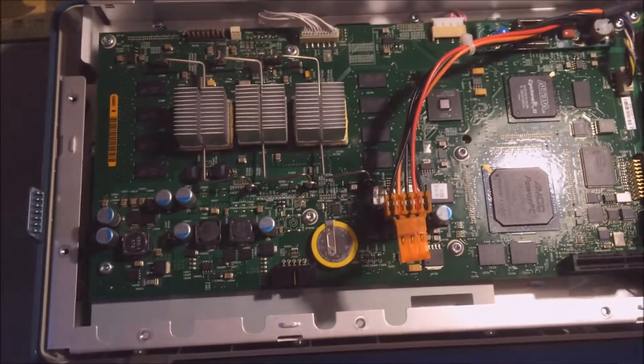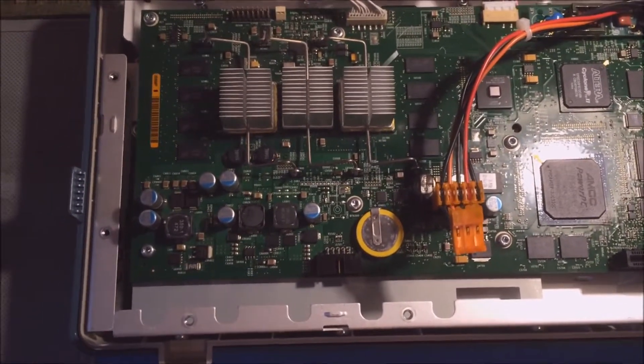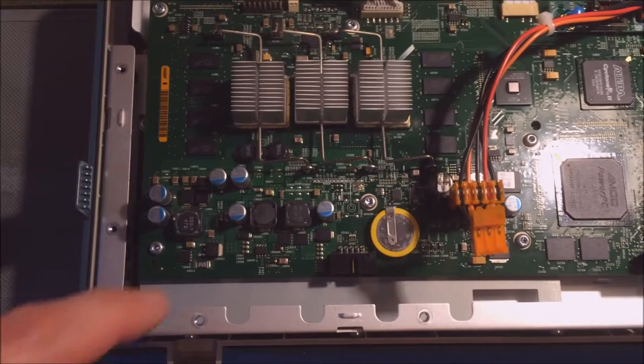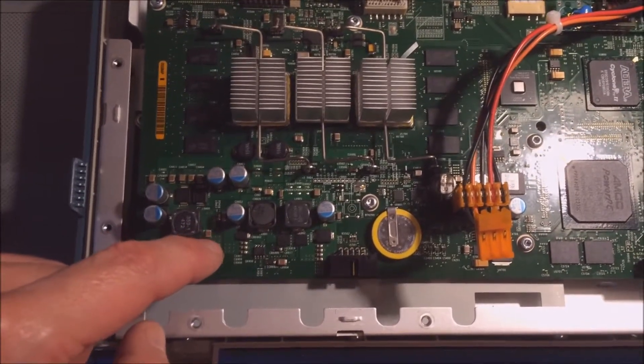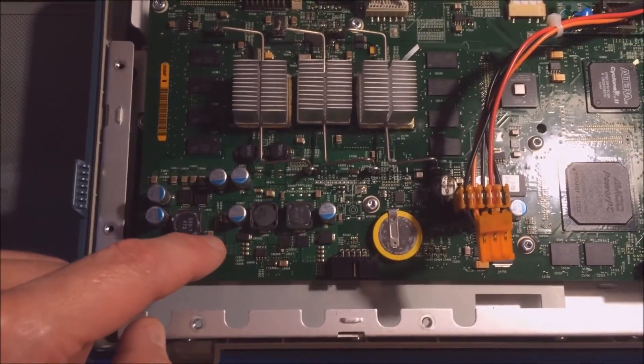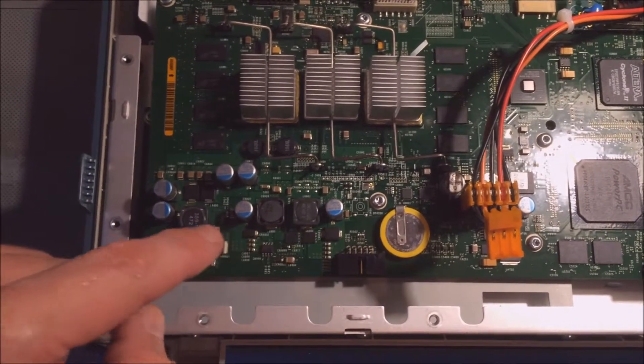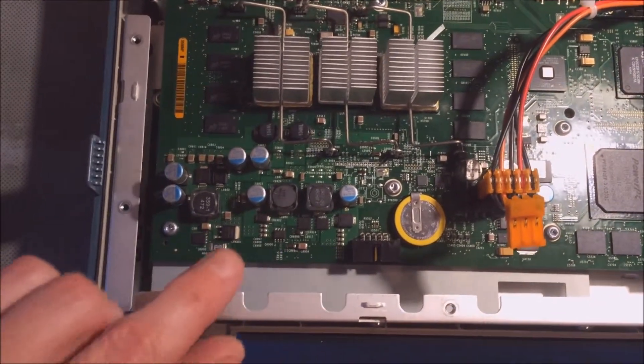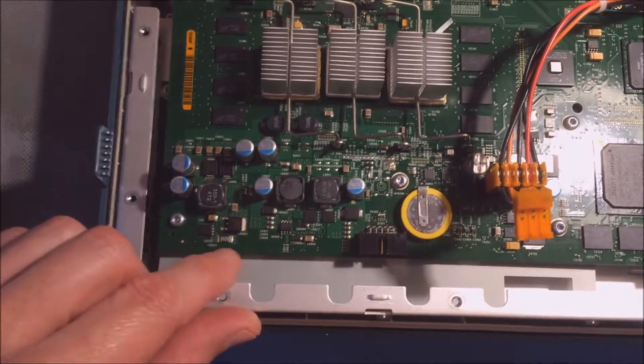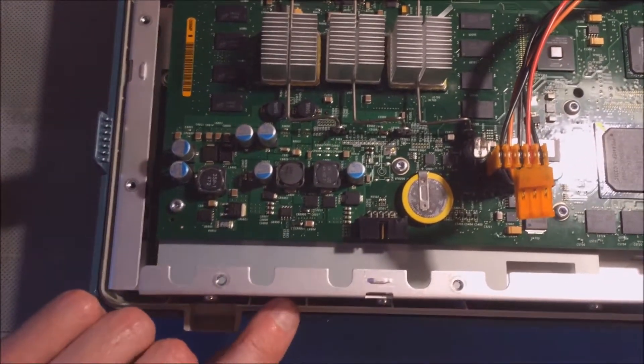Right, when you get inside, unfortunately there are four screws which are hidden underneath the main board and underneath the attenuator board in this position here, which need to be undone to unsecure this frame from the front panel of the scope.